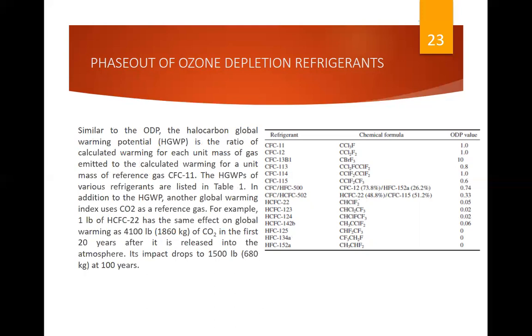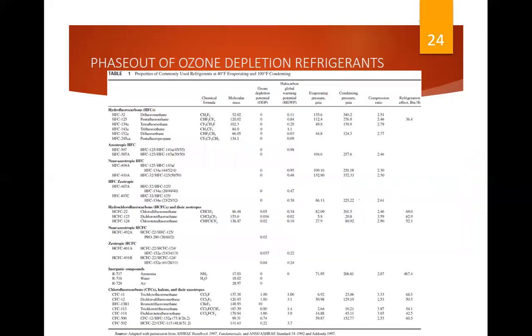Similar to ODP, the halocarbon global warming potential, HGWP, is the ratio of calculated warming for each unit mass of gas emitted to the calculated warming for a unit mass of reference gas. The HGWP of various refrigerants are listed in Table 1. Here is the HGWP and the ODP, which refrigerant it is, and the basis of the values.